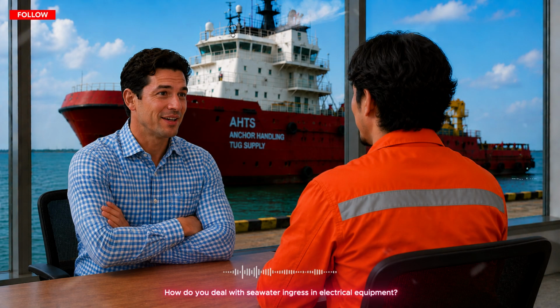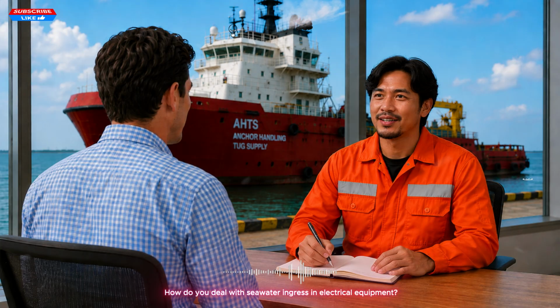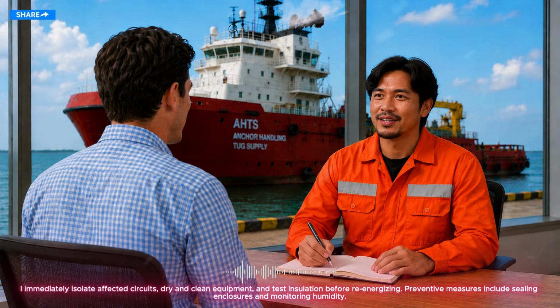How do you deal with seawater ingress in electrical equipment? I immediately isolate affected circuits, dry and clean equipment, and test insulation before re-energizing. Preventive measures include sealing enclosures and monitoring humidity.